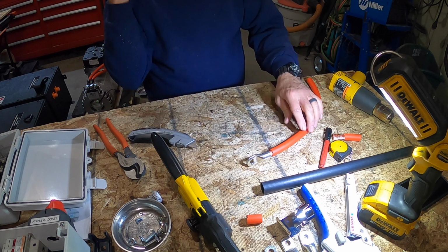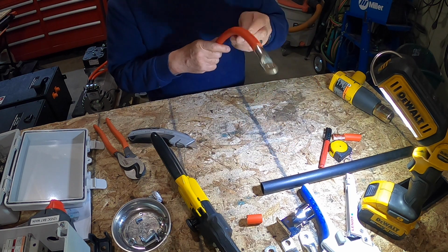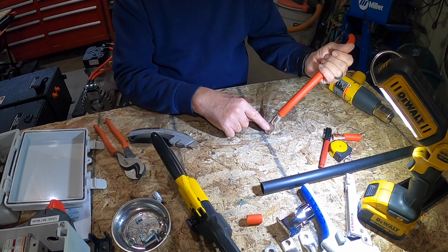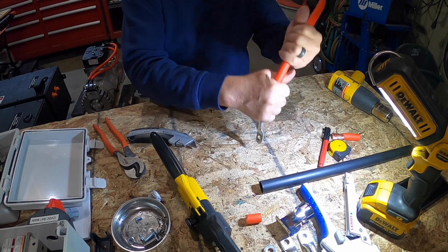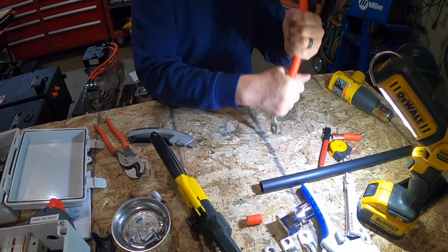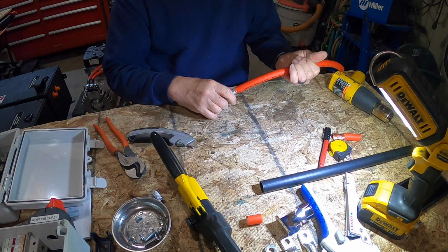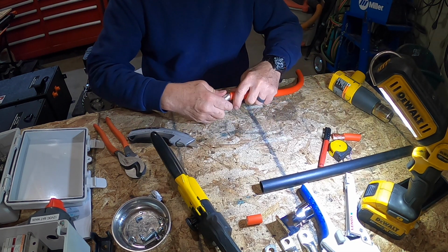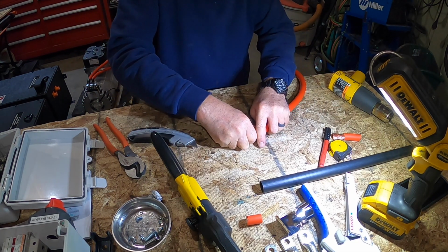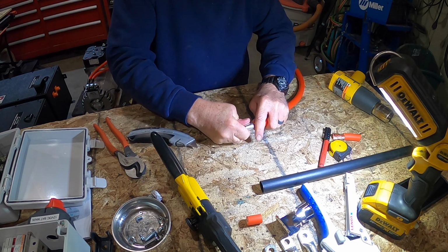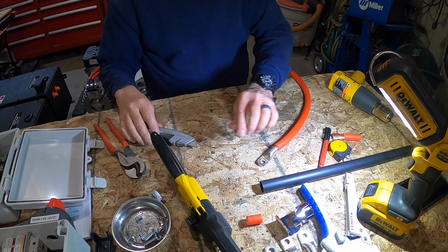And then the other thing I like doing is pounding it down into the head of the lug. So I push the wires down into the head of the lug, and I need to straighten it up a bit. Then I've got a hydraulic crimper - this is a 10-ton crimper that goes up to 2/0 wire.